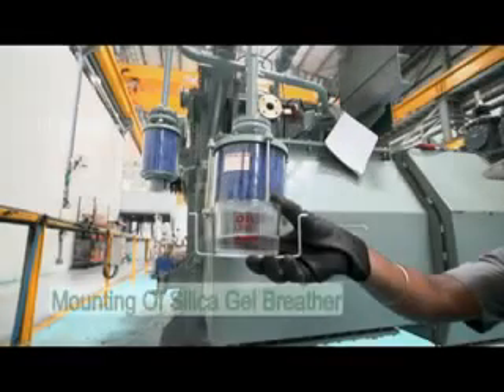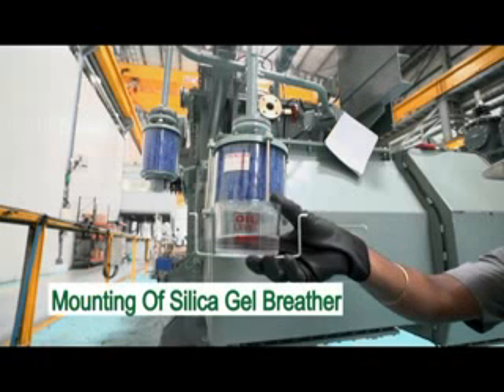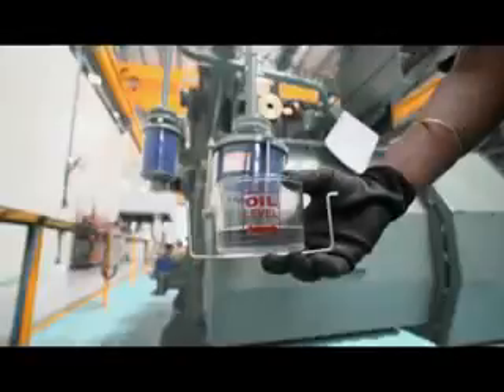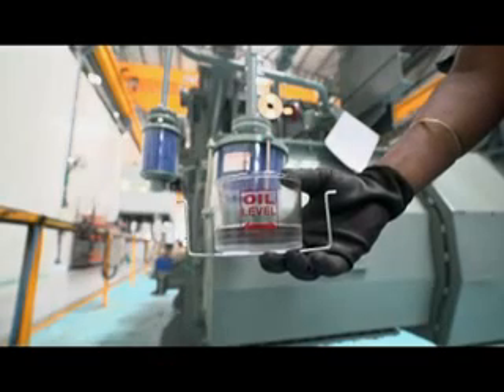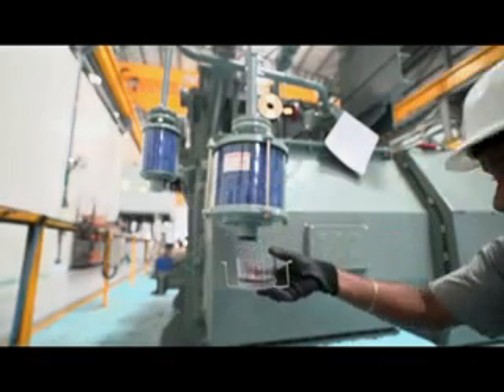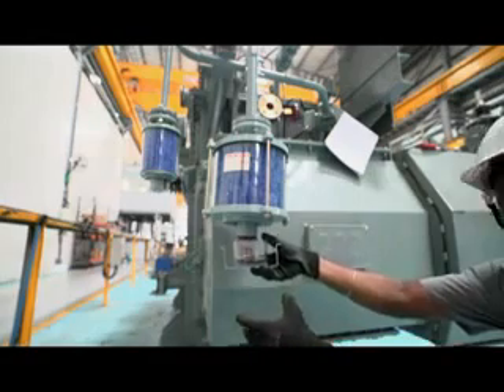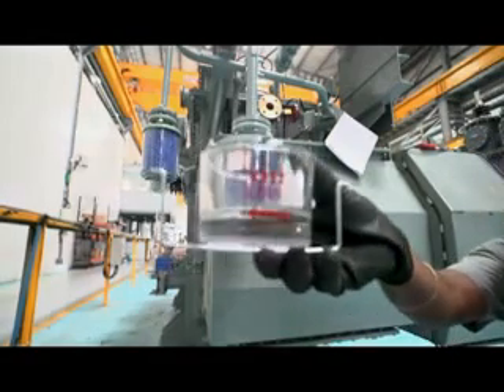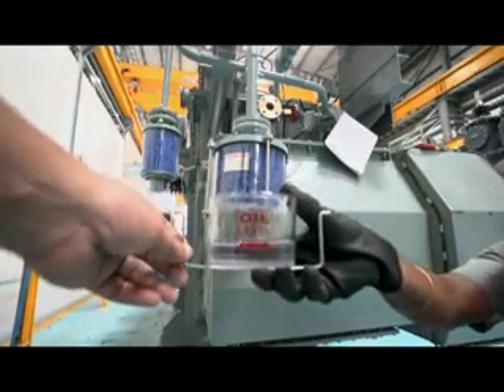Mounting of silica gel breather. Whenever an electrical power transformer is loaded, the temperature of the transformer insulating oil increases. Consequently, the volume of the oil is increased. As the volume of the oil increases, the air above the oil level in the conservator will come out. Again, at low oil temperature, the volume of the oil decreases, which causes air to enter the conservator tank.